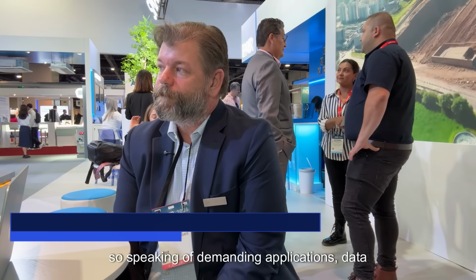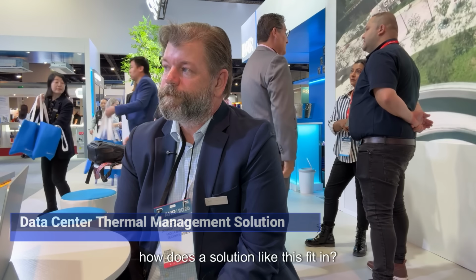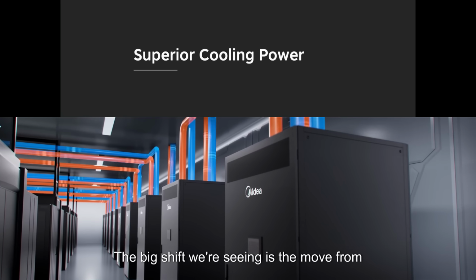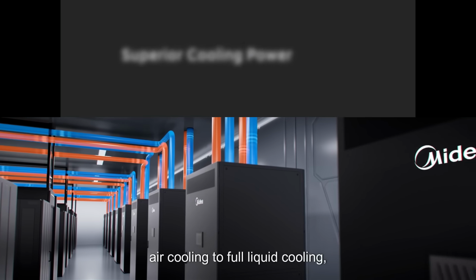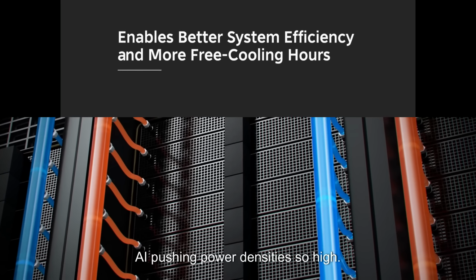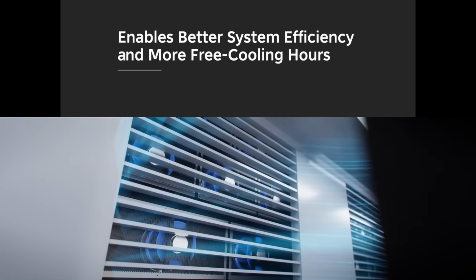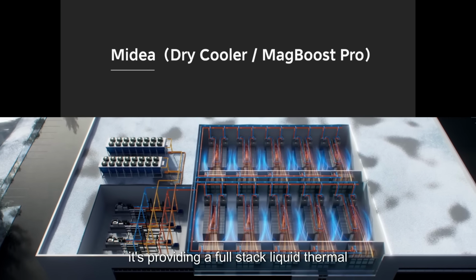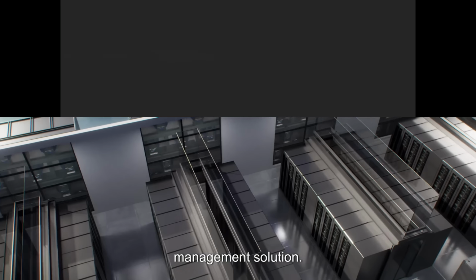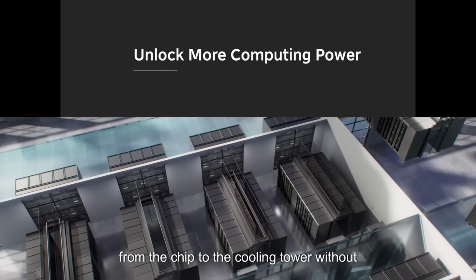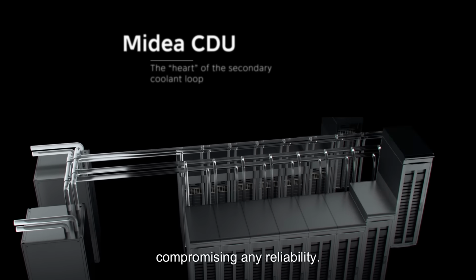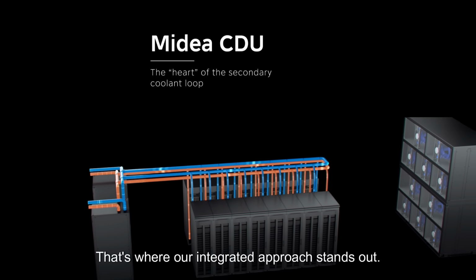Speaking of demanding applications, data centers are a major focus here. With power densities climbing, what trends are you seeing in cooling, and how does a solution like this fit in? The big shift we're seeing is the move from air cooling to full liquid cooling, especially with AI pushing power densities so high. The challenge isn't just a better chiller, it's providing a full-stack liquid thermal management solution from the chip to the cooling tower without compromising reliability.